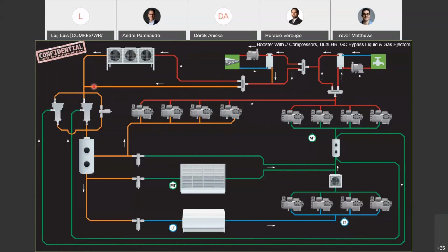We can also manage, what's interesting here, these two other wonky looking valves. And there's also here a suction accumulator. Normally they don't have a suction accumulator, but with some of these systems, what they're doing now is they're allowing all the medium temp cases. Some OEMs are allowing all these medium temp cases to run at 0-degree superheat. And when you run at 0-degree superheat, your suction pressure can float higher. If your medium temp suction pressure can float higher, that means instead of having 450 pounds here, I might have 475 pounds of suction. That means my compression ratio is lower.